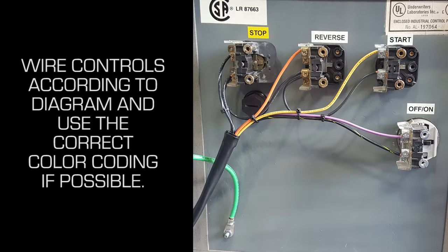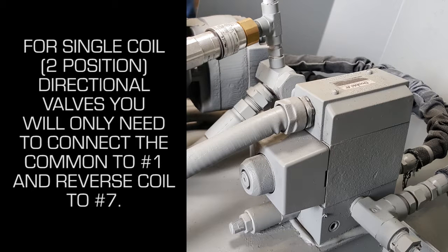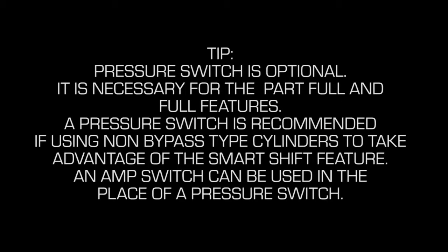Wire controls according to diagram and use the correct color coding if possible. For single coil, 2-position directional valves, you will only need to connect the common to number 1 and reverse coil to number 7. Tip: pressure switch is optional.